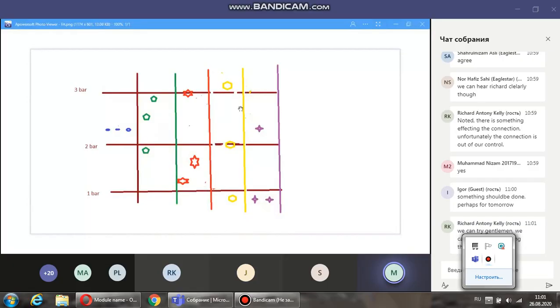When the system is confused, the system will not take the average of all three. It will take the lowest value, but still it does not know whether this is correct. So what it will do, it will give you an alarm. This one is faulty, this one is faulty, and this one is faulty. So it will give an alarm for all three sensors faulty, but take the lowest value. That is how it will behave when there is a difference of more than 1 bar.